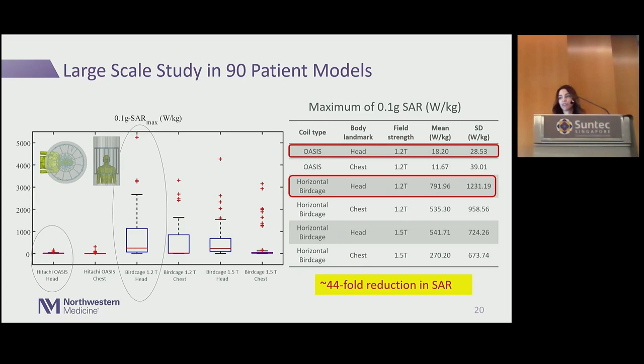We just retune the birdcage coil, a horizontal birdcage to 1.2, meaning to 53 megahertz, and looked at the heating. Still a huge difference. What does it tell me? It tells me that the frequency is not the main contributor. It's the field orientation. The fact that these fields are 90-degree rotated, that's the one that actually causes this reduced heating. And again, this study is published in MRM. And these are all simulation studies. I love them. They give you a really good insight, but you should never try simulation alone.